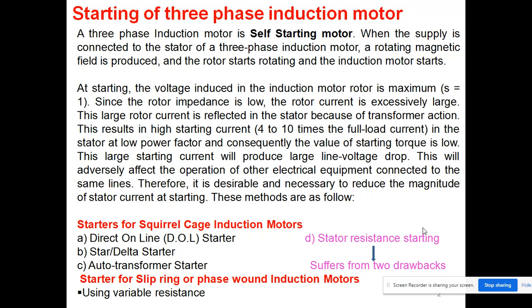It means the rotor impedance is low and the rotor current is excessively large, and this large rotor current is reflected in the stator. Why am I saying it's reflected in the stator? Because of transformer action. This results in a high starting current. It is around 4 to 10 times the full load current at low power factor, and consequently the value of starting torque is low.